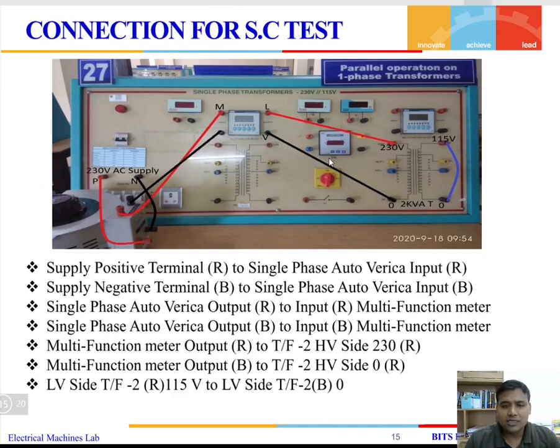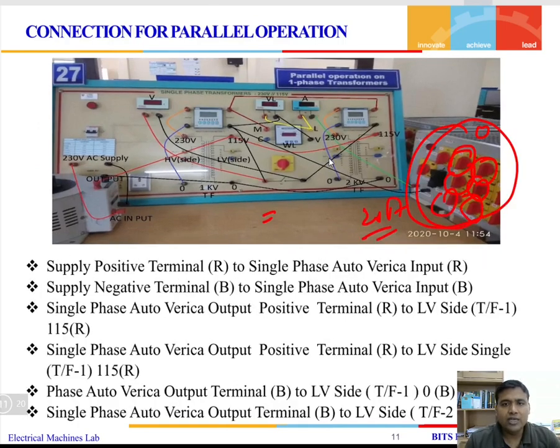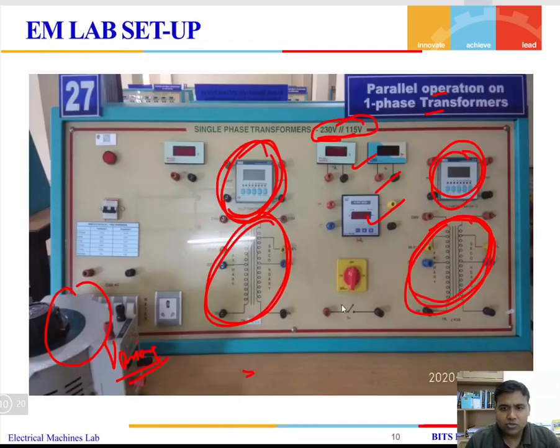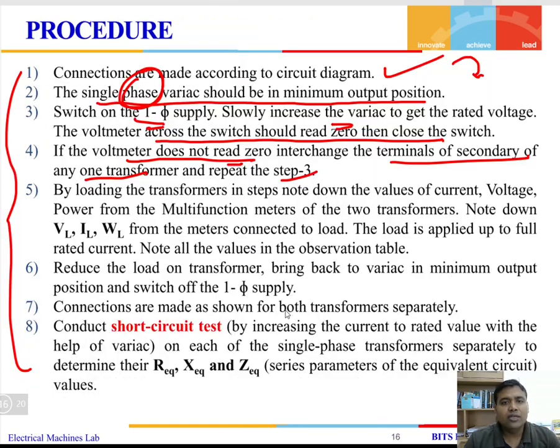So here you can see in this diagram we have a switch which is connected. This switch will be closed only when the voltage shown on the secondary side is 0. Otherwise the switch has to be kept open. Once the voltage is 0, then only you close the switch to do the measurement. And then on closing the switch, you measure the voltage, current, and the power with the help of the multifunction meter.